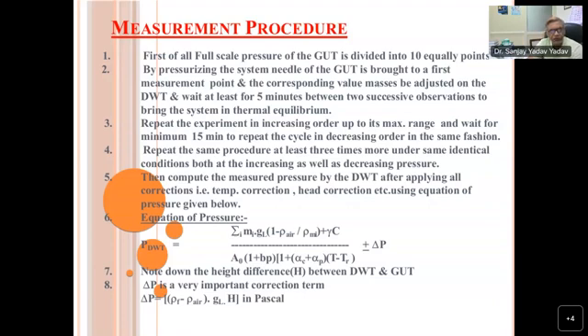Measurement procedure. First of all, full pressure you have to apply to the dial gauge. Normally, we calibrate 10 equal pressure points by pressurizing the system. This methodology I have explained in the figure earlier, but this is the equation: summation of mass, and this is the air buoyancy correction, surface tension correction, and the denominator is the area correction. When your piston A naught is at atmospheric pressure, and this is the distortion correction. B is the piston distortion, and this is the thermal expansion of piston and cylinder. And T is the reference temperature at which A naught is defined, and T is the measurement temperature. You can make all this measurement.